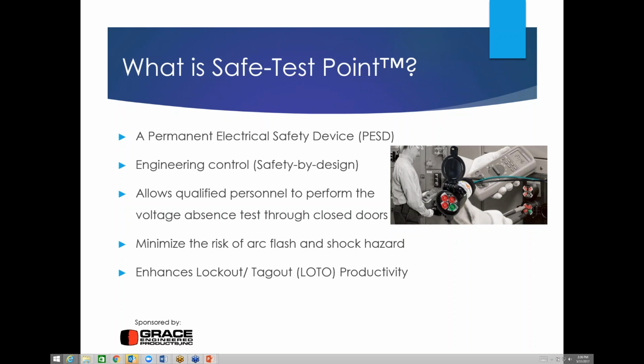So that's very good and very interesting. And I'd like to introduce to you at this point the safe test point. And the safe test point is a permanent electrical safety device which incorporates the engineering control portion of the risk control hierarchy and allows qualified or authorized personnel to perform their voltage testing through closed doors. And what we're actually doing here is minimizing the risk of arc flash and shock hazard, because we're mounting these devices at a level which is comfortable to work at and work on, rather than trying to reach above your head under guarding and get these meter tips in where you can to take those measurements.